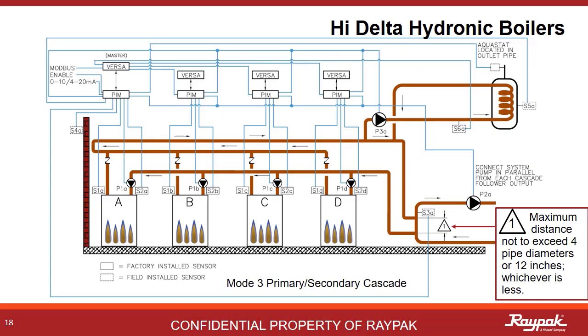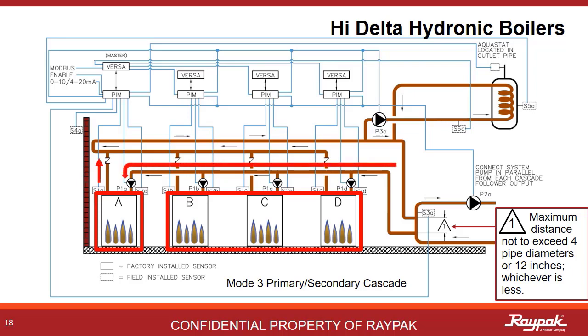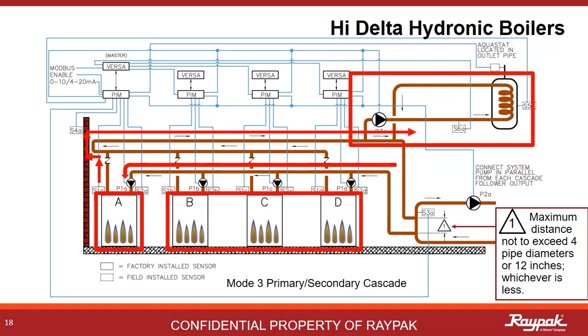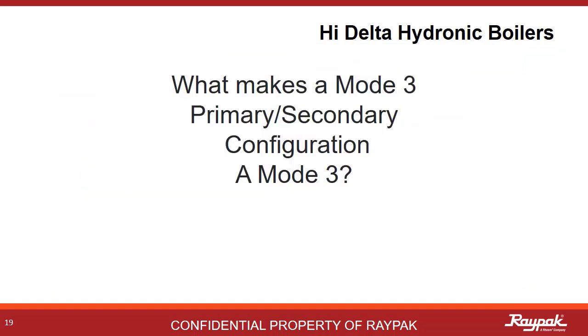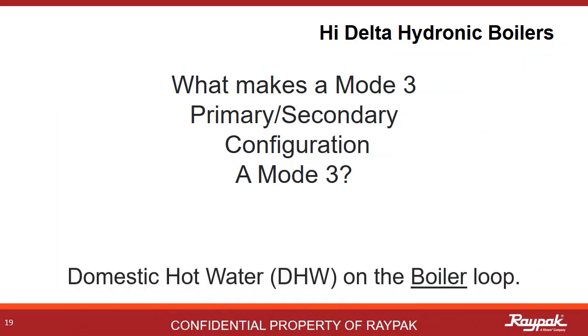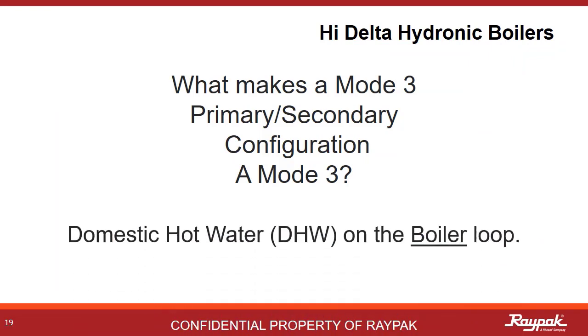Mode 3 can also be run in cascade. Here the A boiler is the master boiler and the others are followers. Being a multiple boiler cascade system, reverse-return plumbing logic applies. It is in Mode 3 because the indirect domestic hot water system is on the boiler loop. So what makes a Mode 3 a Mode 3? It must be plumbed primary-secondary and it must have an indirect domestic hot water system on the boiler loop.